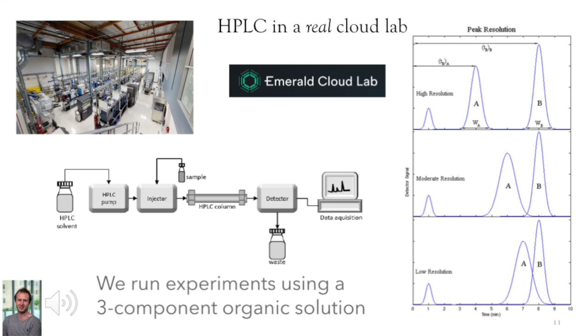In our experiments, we varied 6 parameters, making this a more challenging task. We used HPLC to separate a 3-component organic solution. Thus, unlike with the MALDI-TOF experiment, where we wanted to optimize the signal of a single peak, here we want to resolve the signal of multiple peaks. We use peak resolution to qualify the resulting spectra. Essentially, spectra with peaks that are well separated, tall, and narrow will have high resolution. Since we use a 3-component solution, we want to find 3 highly resolved peaks.